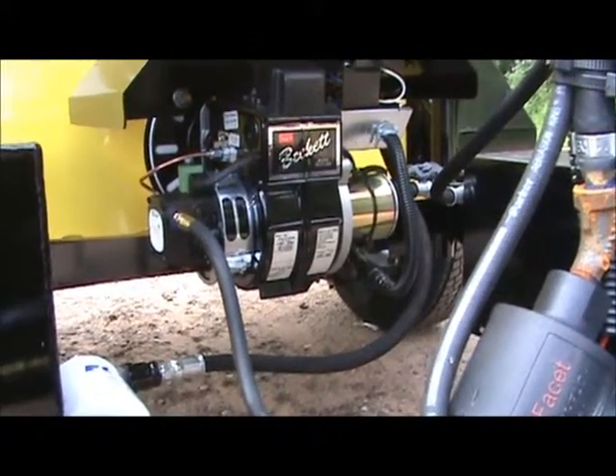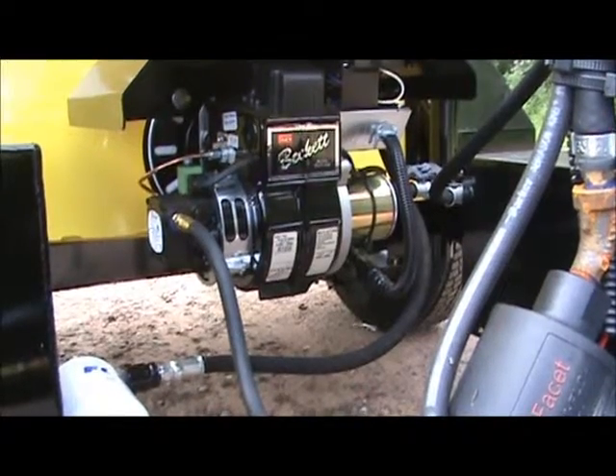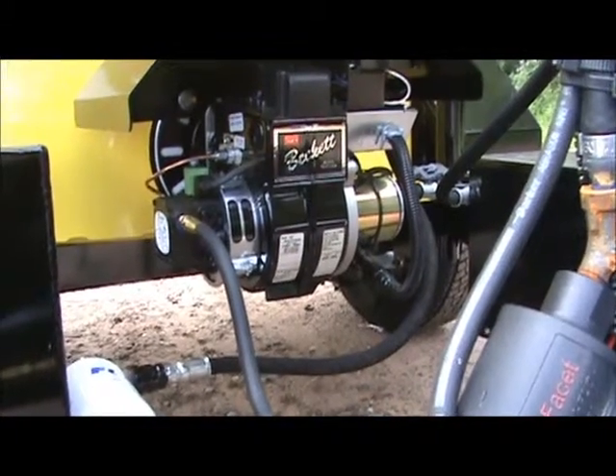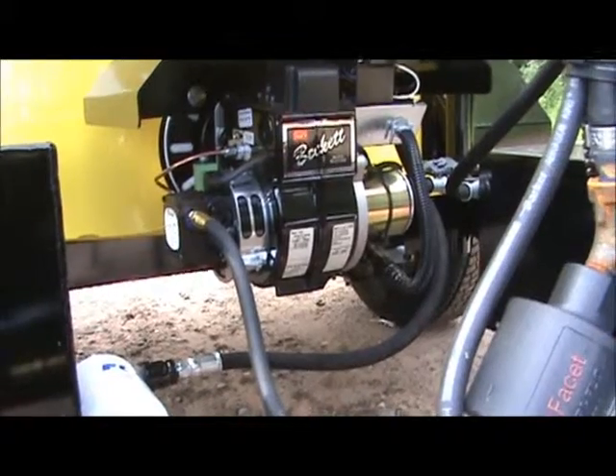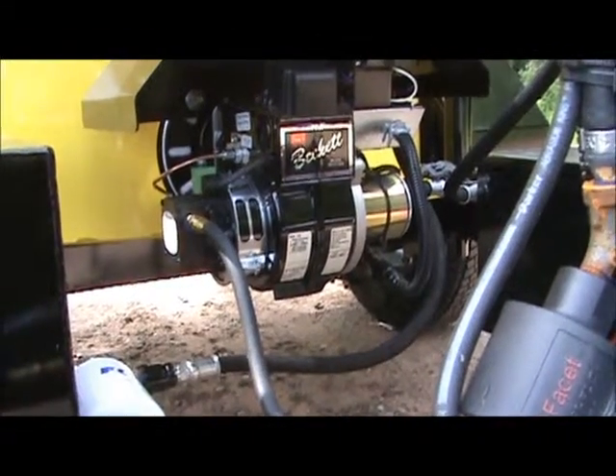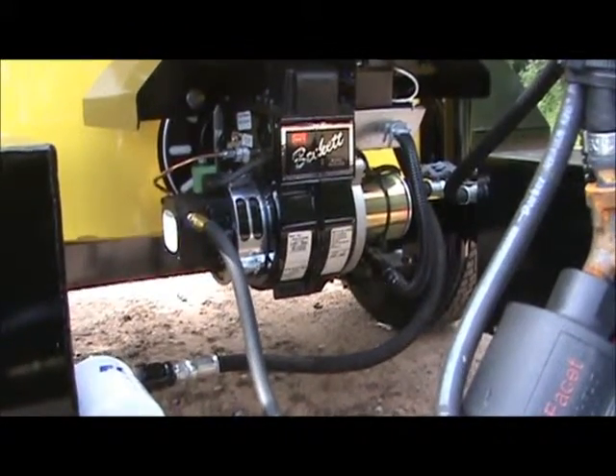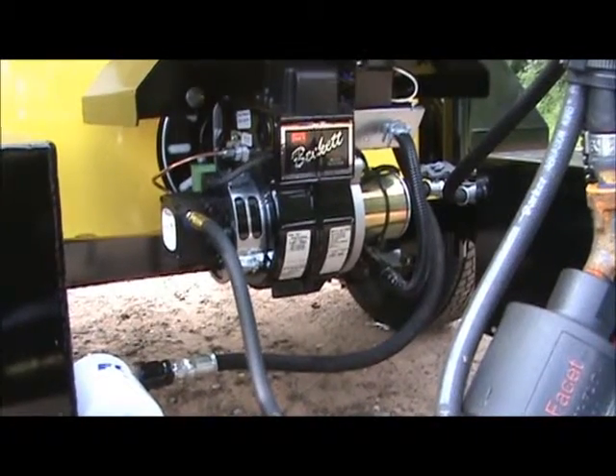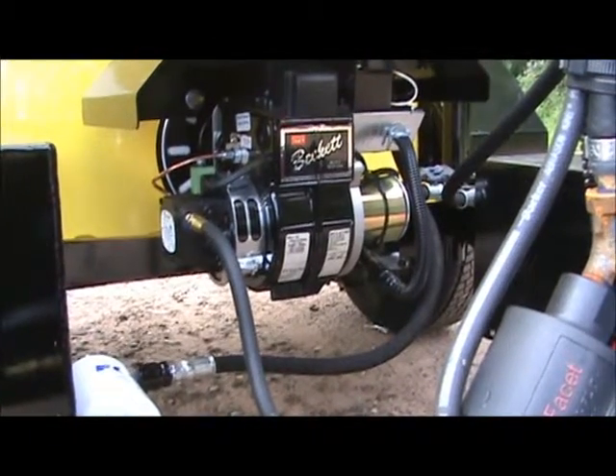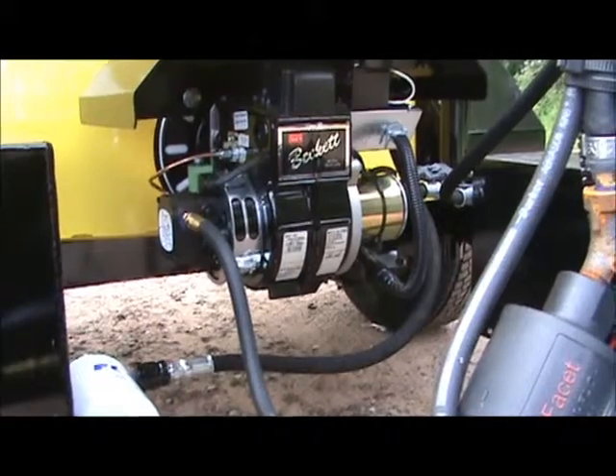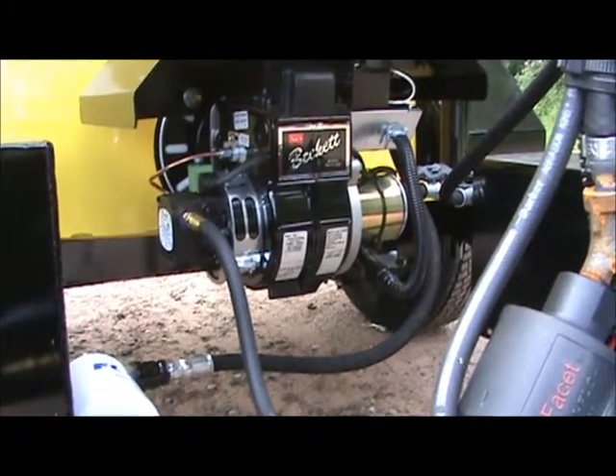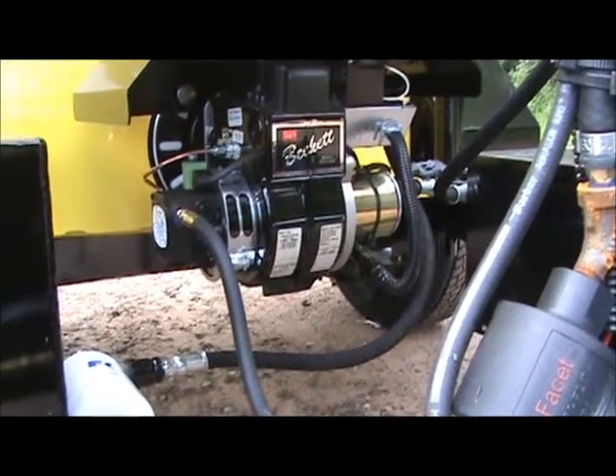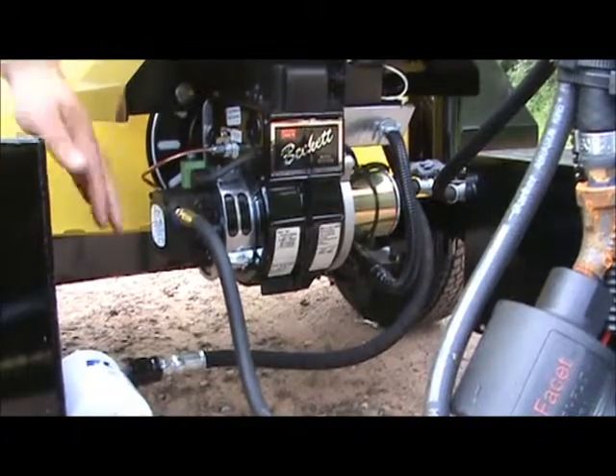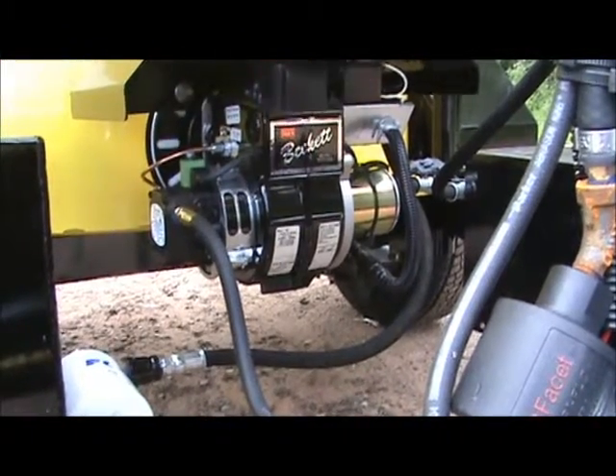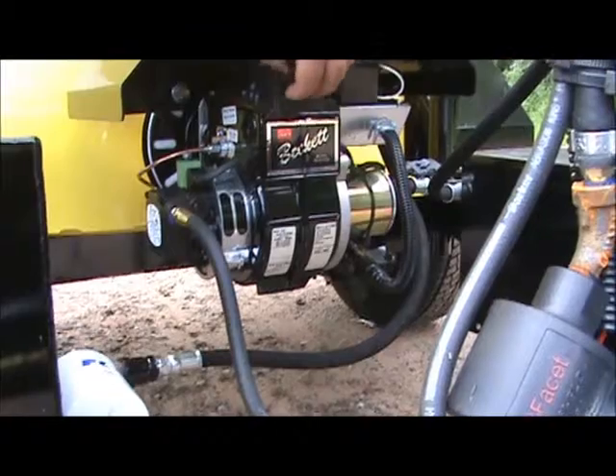If the burner's not lighting, you can hear it hiss, you can hear the spark igniters hiss, you've checked, you've got fuel and it's just not lighting, it probably means that we have it too lean, or there's too much air. So we've got to close those air dampers off. When we set these up at the factory, we actually close all the air down, light it, they start to smoke real bad, and then we open up the air to clean our burner up. So your fuel pump's here, motor, primary control, ignition, transformer.